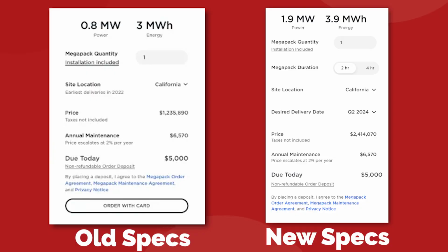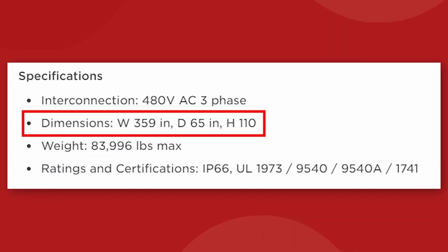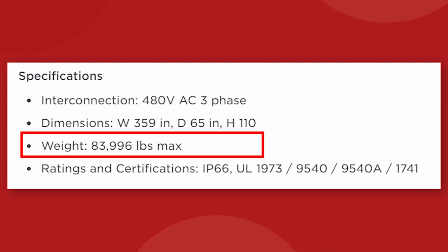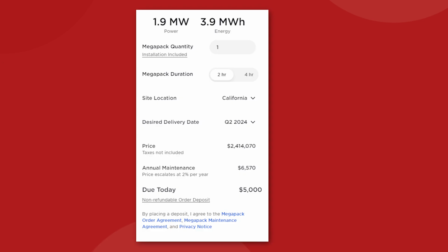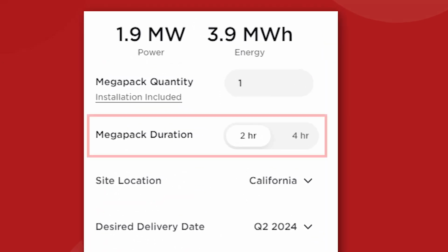The energy capacity of the grid-scale battery is now at 3.9 megawatt hours, up from its original spec of 3 megawatt hours. That upgrade in capacity seems to be reflected in the new product dimensions, with each unit now longer by 6 feet and wider by 2 inches, plus a height increase of 1 foot. The weight also jumps by 64% to nearly 84,000 pounds. There's also a new option to choose between a 2-hour duration Megapack or a 4-hour duration. The longer duration battery just uses half the power output to run for twice the time.